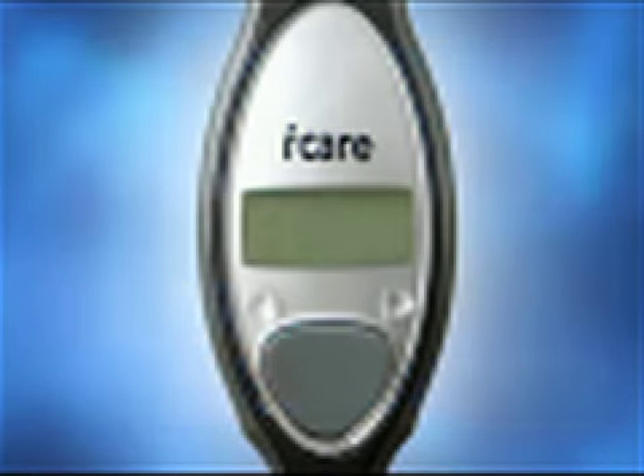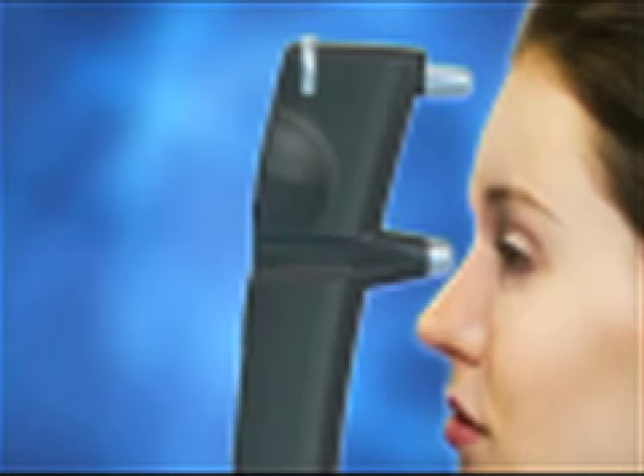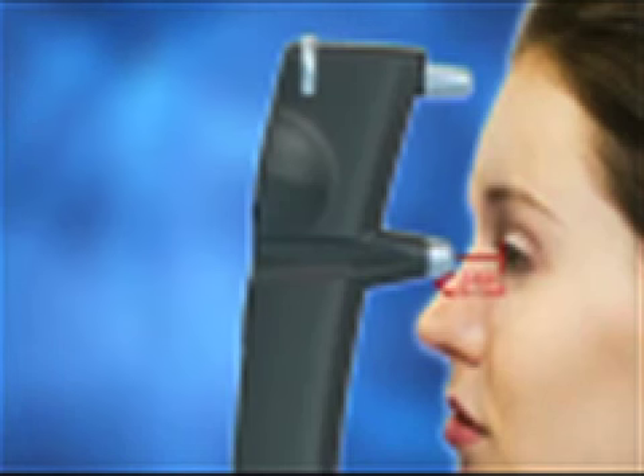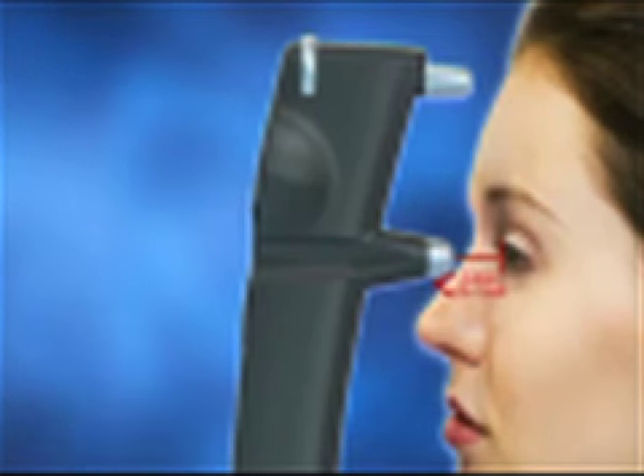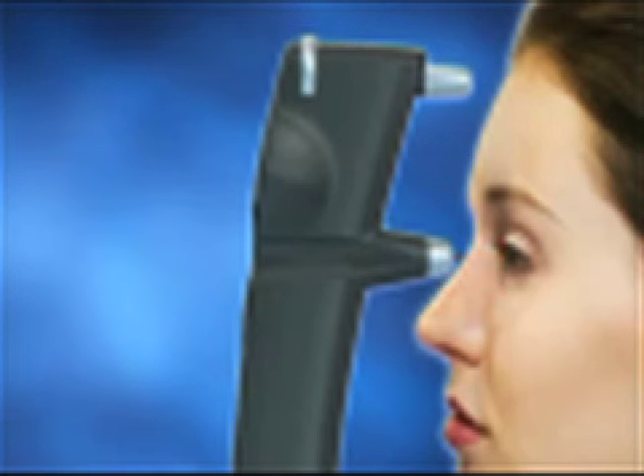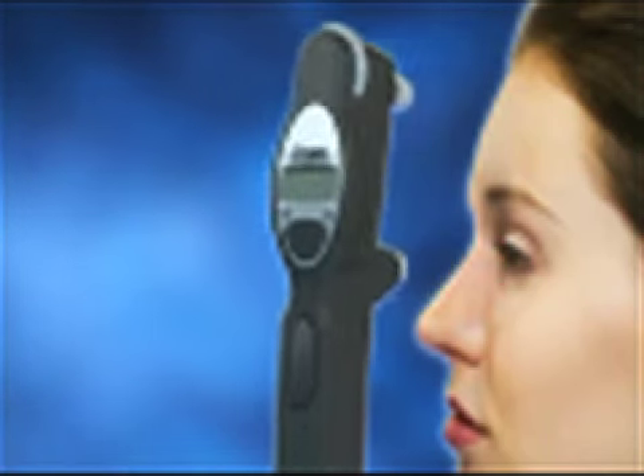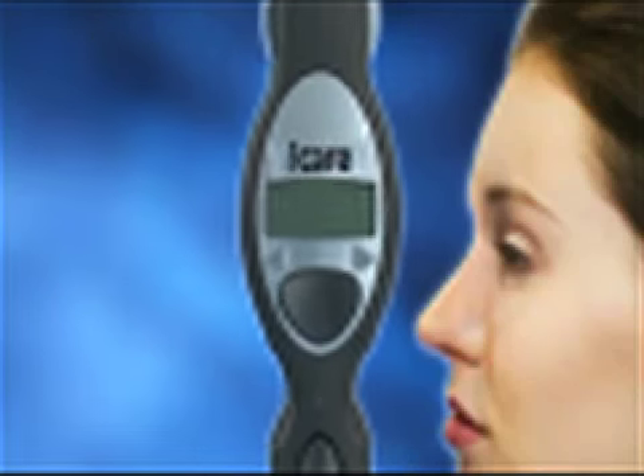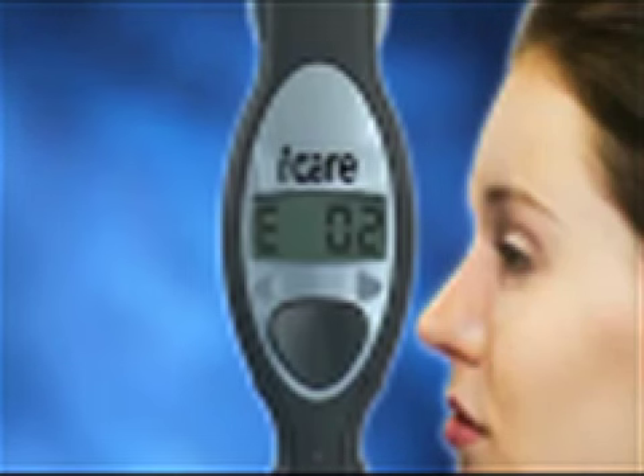Error messages. If the measurement is performed incorrectly, the icare tonometer will always beep twice and give an error message reading, which will indicate the error. For example, if the tonometer is held too far from the eye, the probe may not reach it. This will be indicated by 2 short beeps after the measurement and an E02 reading on the display.